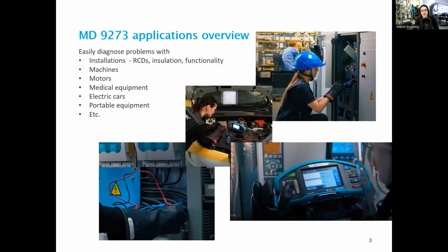The overview of the applications and in general locations where both MD9273 and the earlier 72 can be used. So the clamps are mainly meant for work in installations in low voltage range. And here we have the full selection. They can work in basically any installation in this range. We're talking about home, office, industry, medical, agriculture, pretty much anything. Leakage current measurements can be used to troubleshoot RCDs. They can be used to troubleshoot the installation and the functionality of installations.